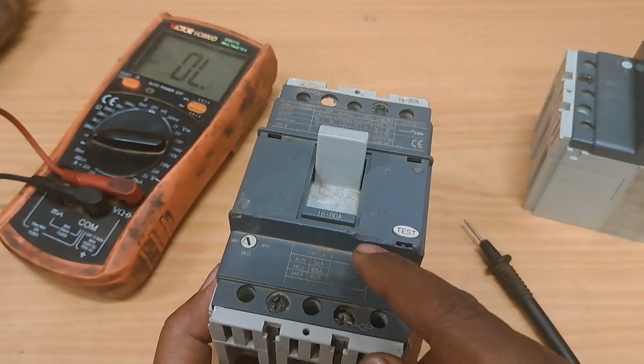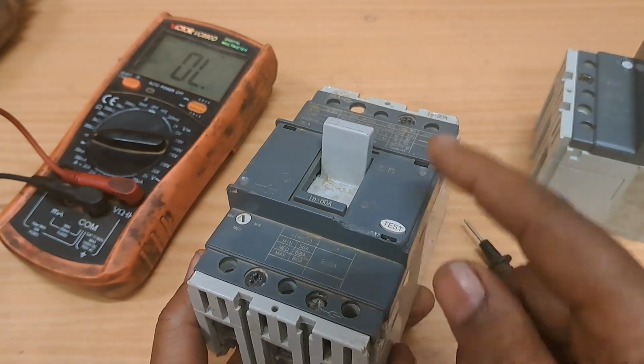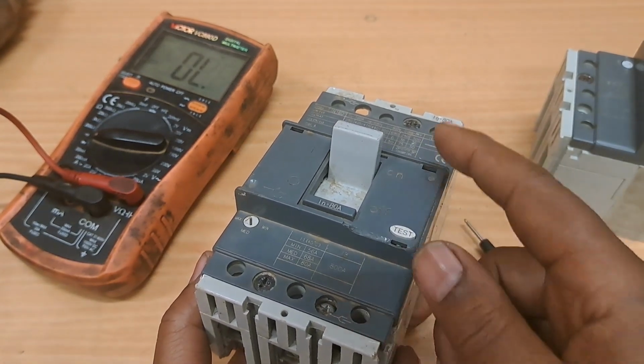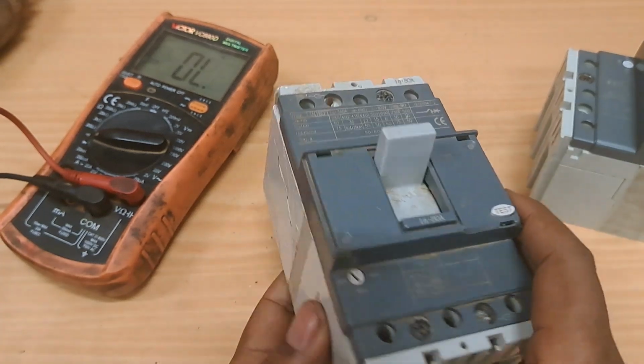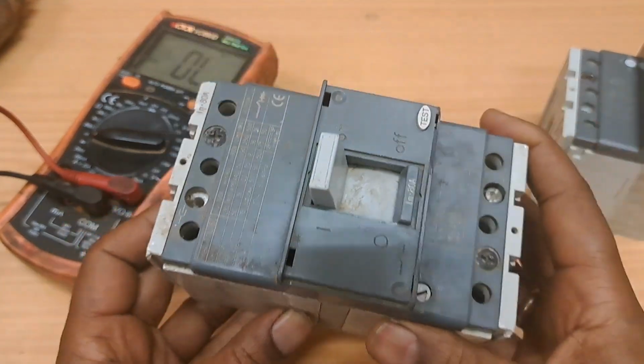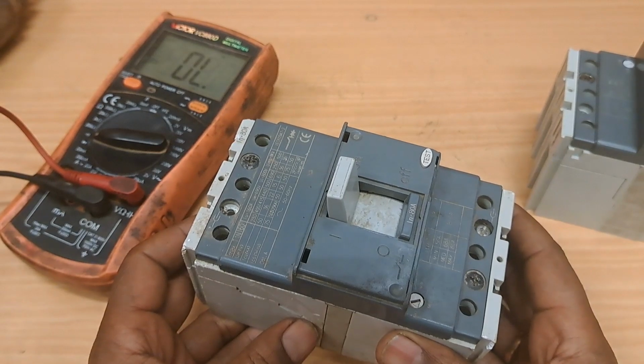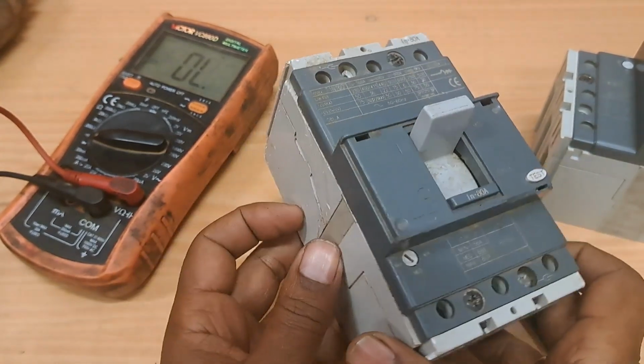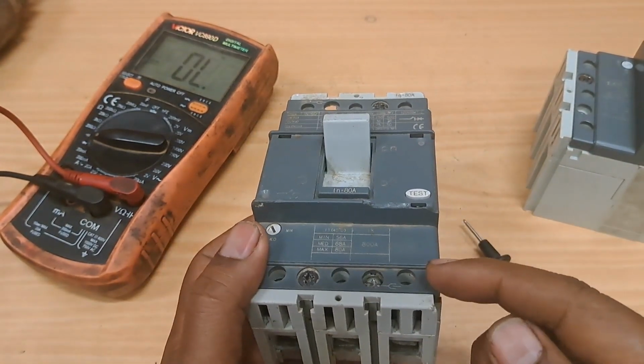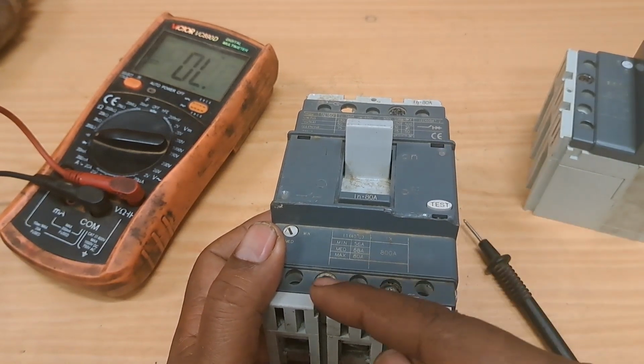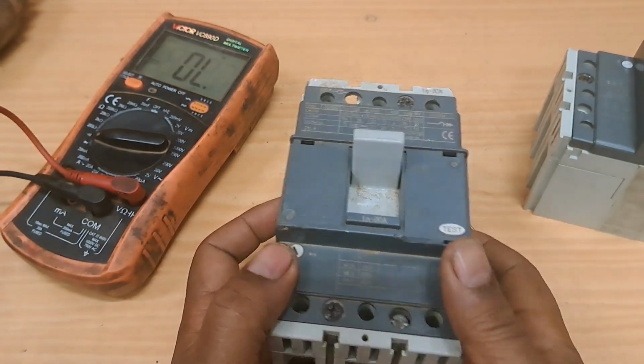Now, when measuring the continuity, if you find that at least one of the terminals has no continuity, then you should stop using these three-phase terminals. Otherwise, it will lead to motor damage. It will lead to blown out motors because of a missing phase. Make sure that all three are continuous.